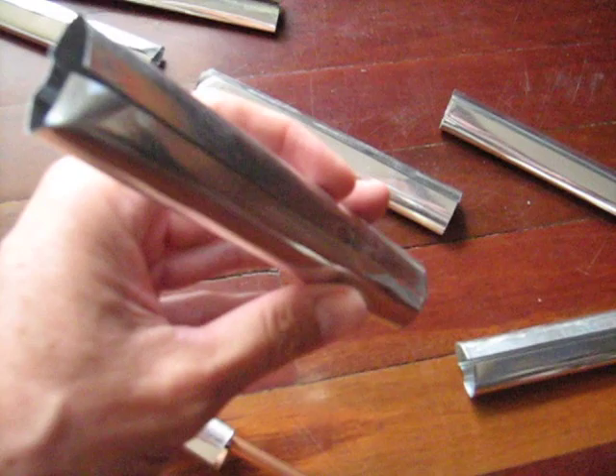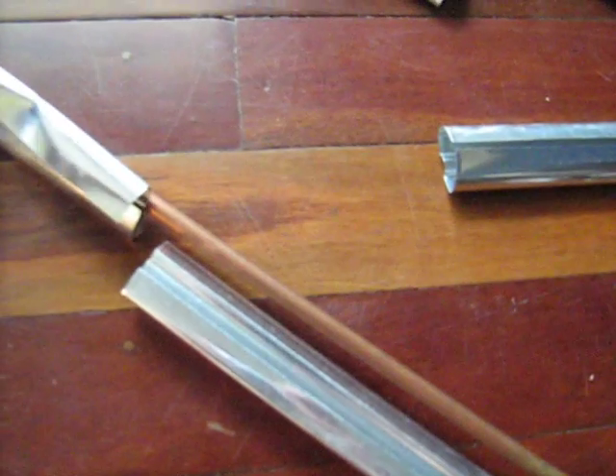You can see it's copper coated, or has a copper sleeve within the glass, which transfers the heat further to these little aluminum wings. The aluminum wings themselves, through this groove, are attached to the pipe. So if you have aluminum wings which look like this, you can imagine the heat transfer is not really that great.